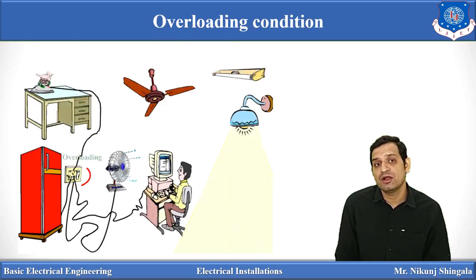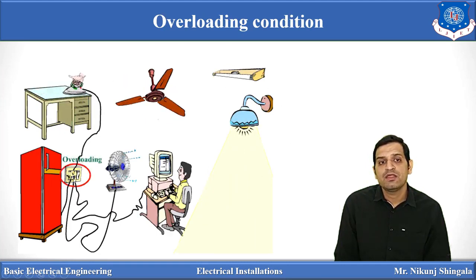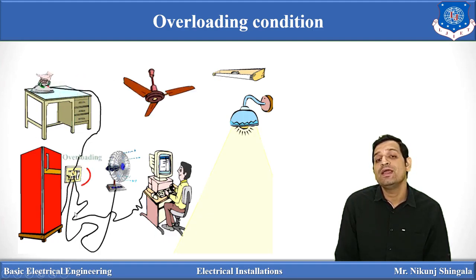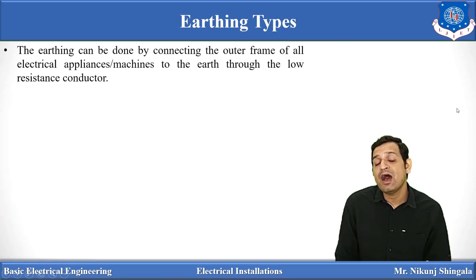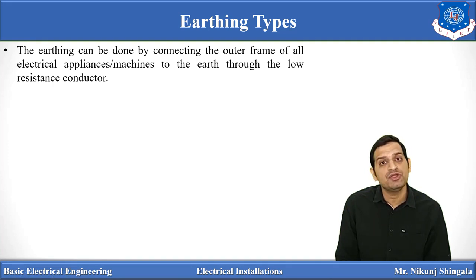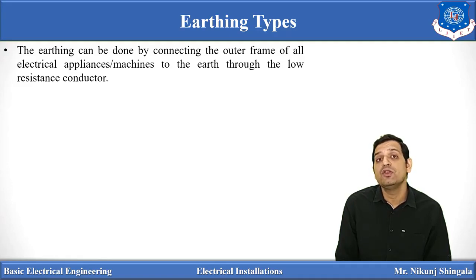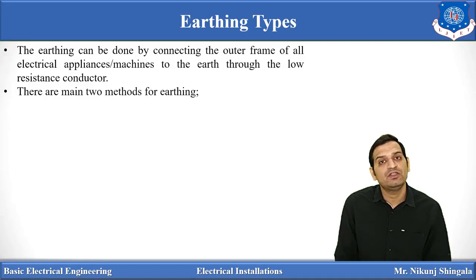When overloading occurs, you can see that a number of devices are connected on a single switchboard, so overloading can occur. There are two types of earthing. Earthing can be done by connecting the outer frame of all electrical appliances or machines to earth through a low resistance conductor. The conductor used for earthing should have low resistance, and we should make arrangements to decrease that resistance as much as possible. The two types of earthing methods are: pipe earthing and plate earthing.